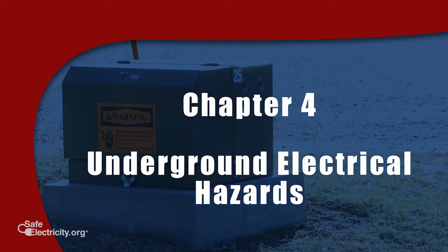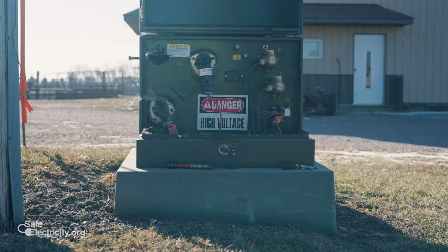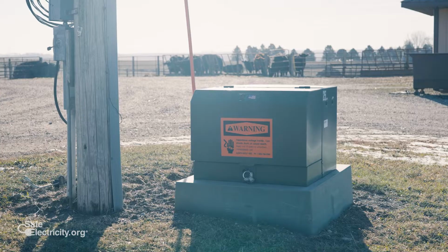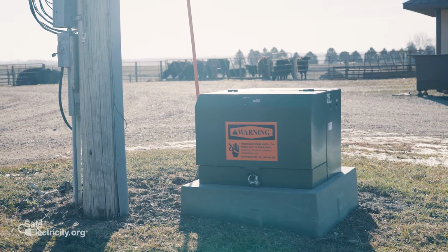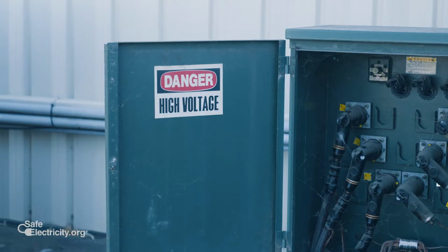Underground utilities—even though it's just a green box in someone's yard—are a transformer just like the ones you see up on a power line pole. It's got high voltage coming in, transforming that power into usable voltage for the member. It's a pad mount transformer in a box full of mineral oil. If it's compromised, hit by a car or a tree falling on it, there's a high likelihood the transformer will stay energized. Upon touching that transformer, you are touching an energized piece of equipment, and that can be fatal. We're starting to see more and more underground utilities all the time, and a lot of times they're in the road right-of-ways, which makes them prone to being hit by cars.